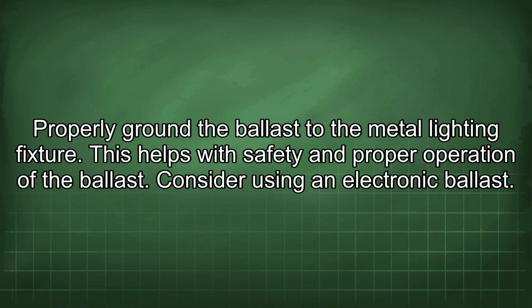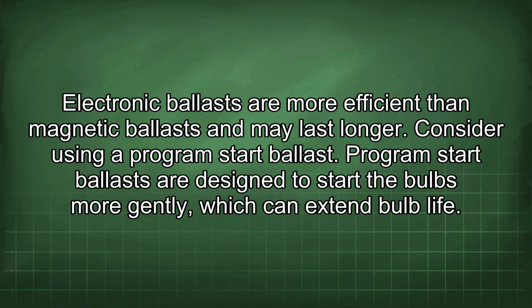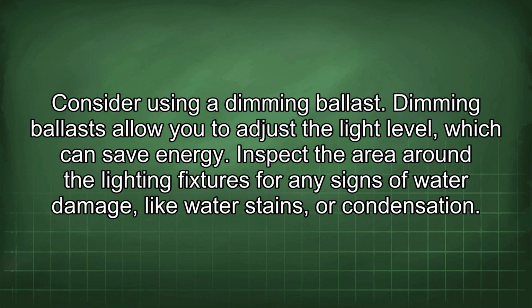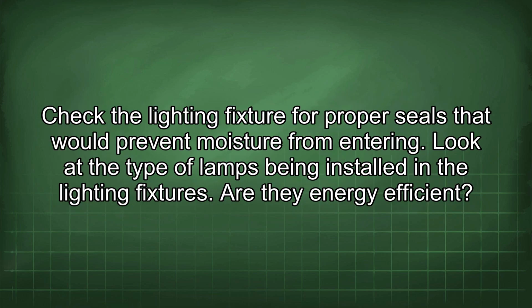Consider using an electronic ballast. Electronic ballasts are more efficient than magnetic ballasts and may last longer. Consider using a program start ballast. Program start ballasts are designed to start the bulbs more gently, which can extend bulb life. Consider using a dimming ballast. Dimming ballasts allow you to adjust the light level, which can save energy. Inspect the area around the lighting fixtures for any signs of water damage, like water stains or condensation. Check the lighting fixture for proper seals that would prevent moisture from entering.